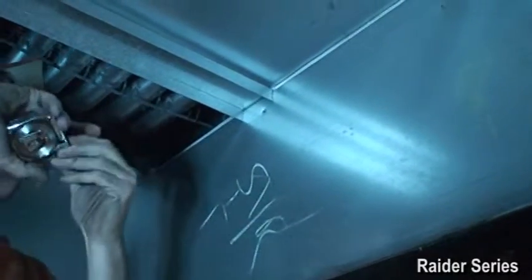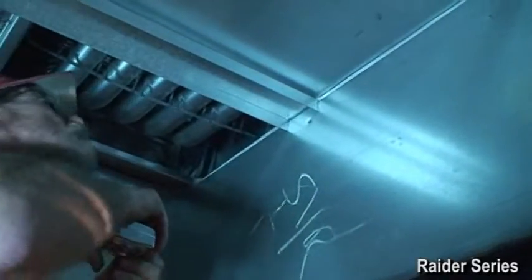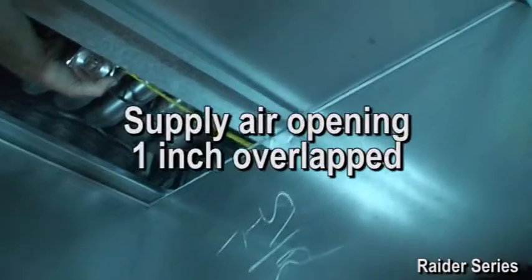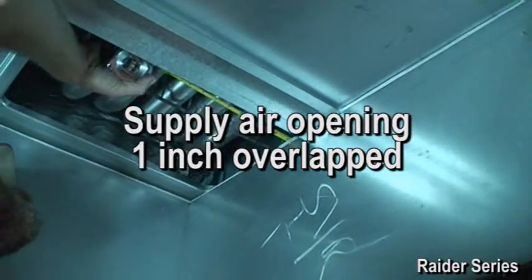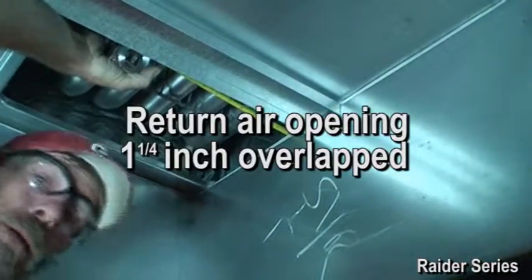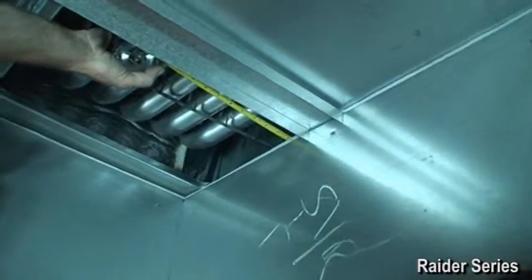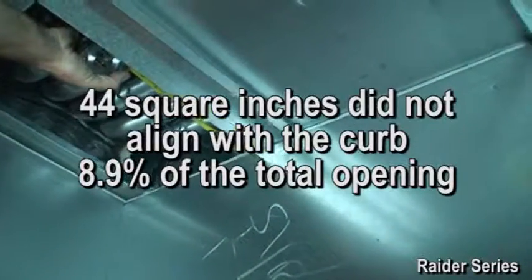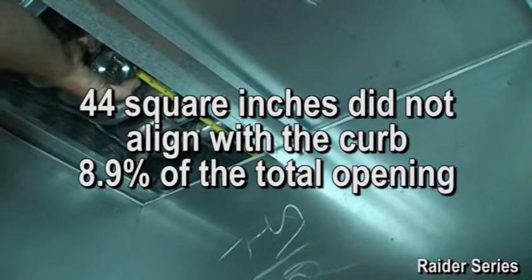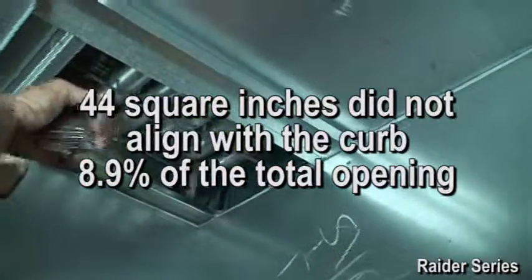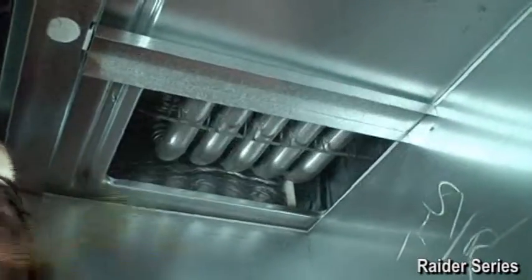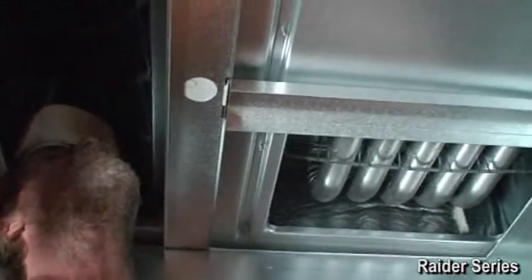Once the team was able to work around this lip issue, they noticed that the unit was not a direct fit up to the supply and return air ducts. In fact, they were surprised to see that the supply opening had a full 1-inch overlap and the return opening had a full 1 1/4 inch overlap. To put that in perspective, that is a total of 44 square inches that did not align with the curb, or 8.9% of the total opening. That not only creates unaccounted for pressure drop, but possible loss of performance.